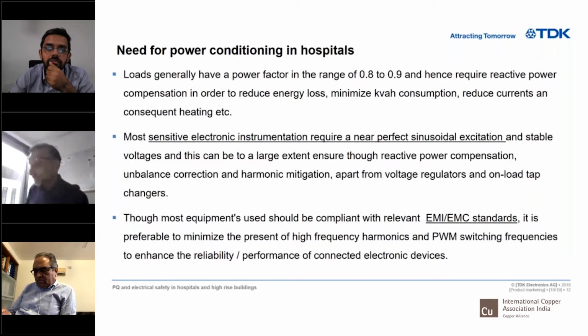And one of the cases where I learned this was one of the largest clinics I've seen in my life. It's almost like a 7-star hotel. It's in the Middle East, a 7-story large hospital. They had installed some active filters because they had harmonics. But after the active filters were installed, they had a lot of equipment malfunctioning because of the EMI, EMC coming out of the active filter itself, because of the PWM switching frequencies. So even the selection of the power conditioning device is also very important.